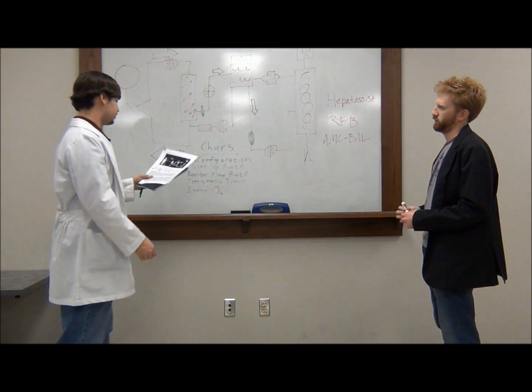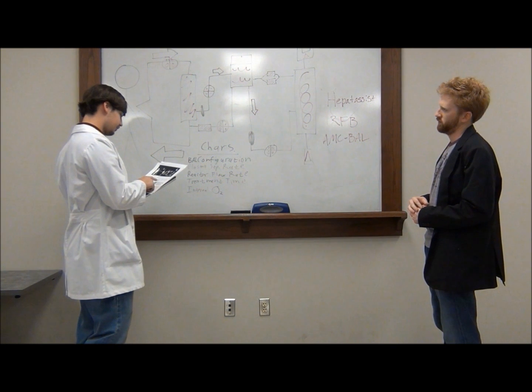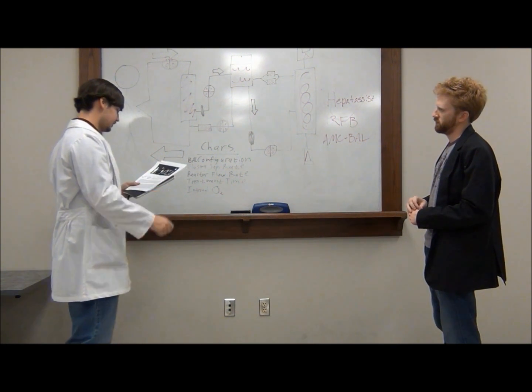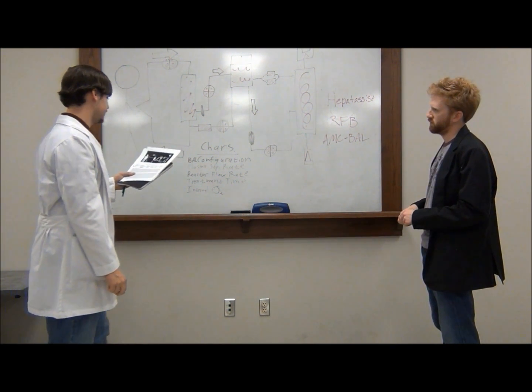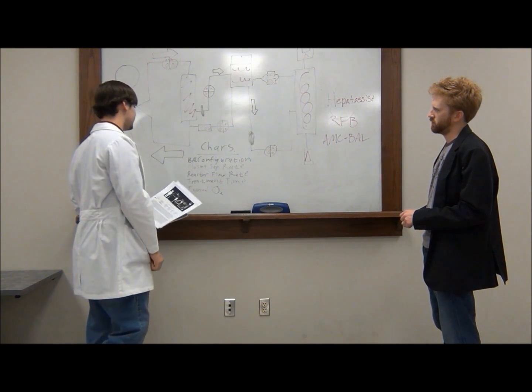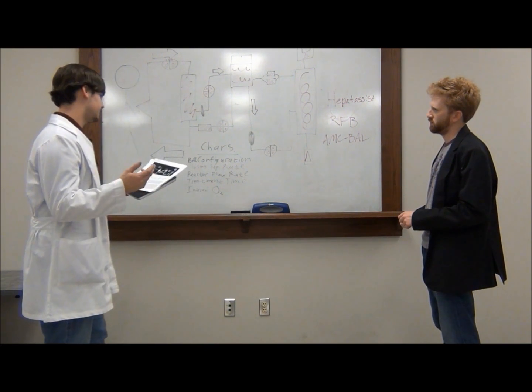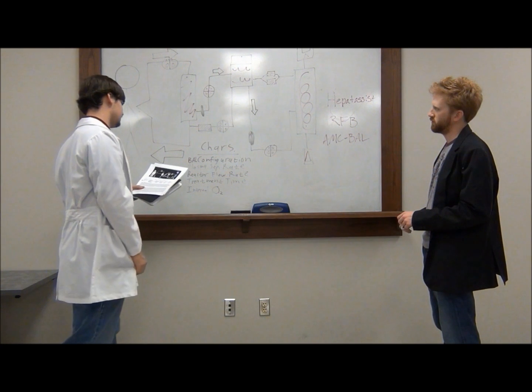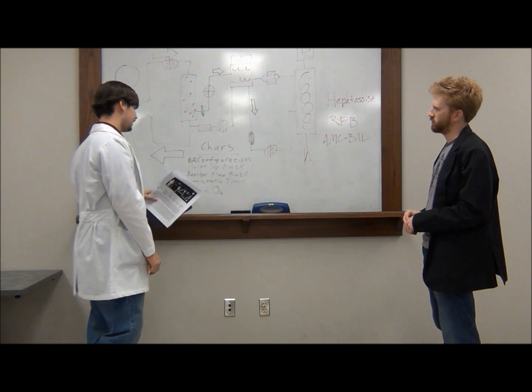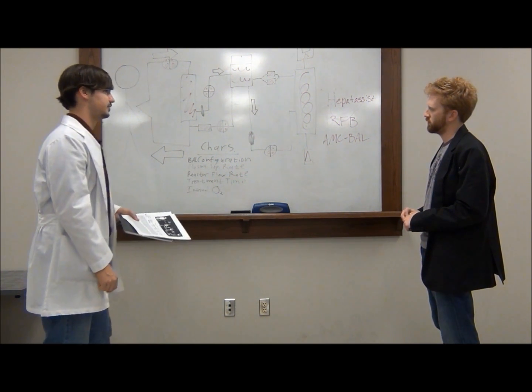Tell me more about this AMC-BAL. Well, the plasma separation rate for the AMC-BAL is 45 milliliters per minute. The reactor flow rate is 225 milliliters per minute. The patient, as of right now, can be treated up to 24 hours, and it has an internal oxygen system.